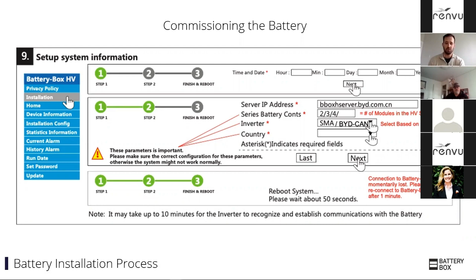At that point, you don't have to commission it again. Even if you turn off the battery, you could turn it back on later - it knows what it's got going on. Obviously if you make a change, like if you change inverters, you'd have to go back and recommission. If you changed how many modules were in the stack, you would also have to recommission.